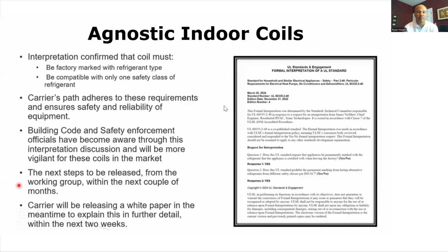Since that point in time, there were some discussions and legalities with that, and the compromise ended up being that ADP was not going to be able to send that coil out like that, because people might lie and say they're going to put it on 410A and then go ahead and put it on R-32 and not buy any of the safety controls that would have been provided with the more expensive R-32 version.